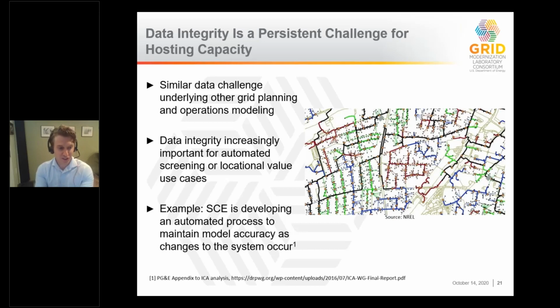Hopping back into the presentation, I want to flag how data integrity is a persistent challenge for hosting capacity. This is similar to ADMS adoption or other systems that rely on system data being available and accurate. As we think about more advanced use cases, like approving interconnection applications through an automated method without someone reviewing the data, this data integrity issue becomes even more prominent. There's an example of Southern California Edison developing an automated process for improving accuracy and accounting for system changes, since the distribution system is dynamic and changes constantly due to storms, upgrades, or other factors.